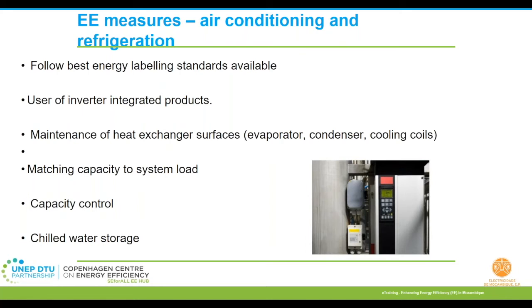Matching capacity to system load. More often, we see that people tend to over design than the required. So that again leads you to inefficiencies due to partial operations and all. So you need to make sure that your system capacities and cooling loads match. Capacity control, I've talked about.